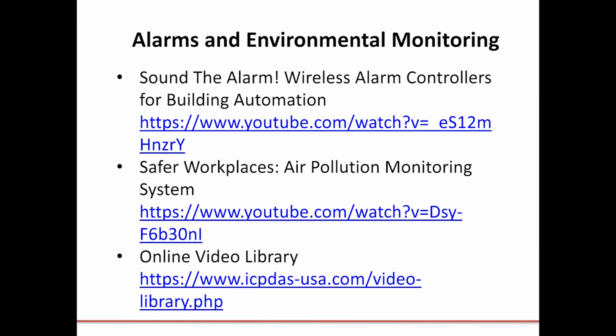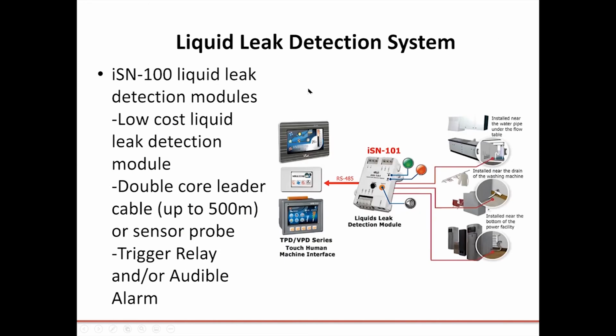There's one more thing I want to talk about that's important if you want to prevent damage to machinery, property, and the building itself, and that is water leakage. The ISN 100 series are low-cost, intelligent liquid leak detection devices that can directly control relay output, with no additional conversion module needed. The ISN 101 can easily be integrated into a Building Automation System or SCADA. These modules use a double-core leader cable with lengths up to 500 meters, or a leakage sensor probe, to detect liquid leaks. If a liquid is detected, the controller immediately activates the output relay, with normally open, normally closed, passive output signal. You can use this to sound an alarm, start a light, or tell a machine to start or stop. This series is your first line of defense against water damage, and is a great solution for common areas in offices and multi-unit housing, or anywhere a leak would cause a lot of damage.